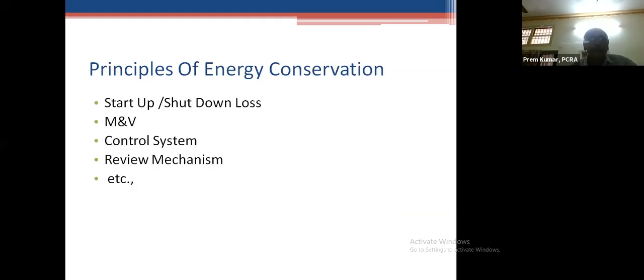So again, startup and shutdown loss is in. Measurement and verification system should be possible. The control system should be in place in the initial stage itself. For example, you want to check up the control system, let us say the temperature control system. The PID control system or the stage control system should be there from the beginning itself. Similarly, you take the nature, for example, air conditioning. It will work more in summer. It has to work less in winter. So we should have a mechanism for RPM reduction. For example, VFD should be in place.